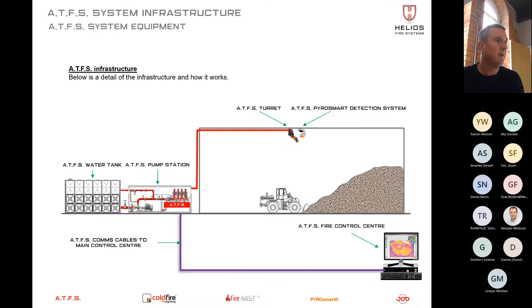So normal daily operation. We can see here the camera scanning the entire area. One camera can probably cover an area 100 meters square. One cannon can cover an area anywhere 50 meters in diameter. So I can throw water from any one position inside a building 50 meters. But that can obviously change dependent on the setup inside the building. If we have push walls, if we have any fire breaks, if we have any areas that create blind spots, then we need more cameras, more cannons. But dependent on the size of the building, we should be able to get the camera and the cannon system up at height and minimize the amount of infrastructure required to protect that building.